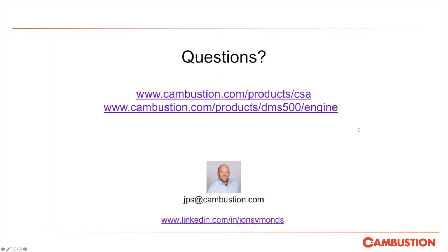This question here, which DMS model can handle PM2.5? It's actually the same model. It's just had some extra hardware added to it to change some of the voltages inside. And usually we make it switchable between 1 micron and 2.5 micron.